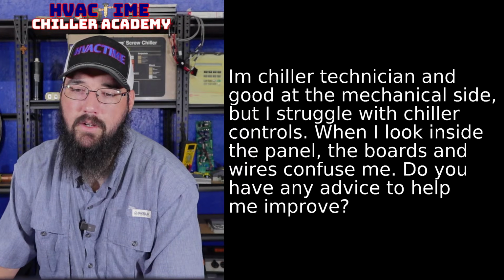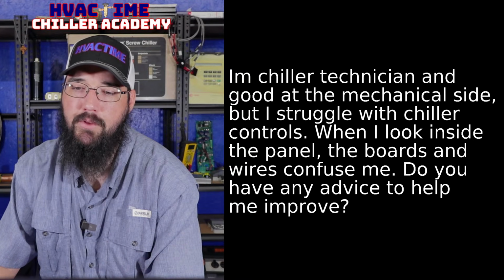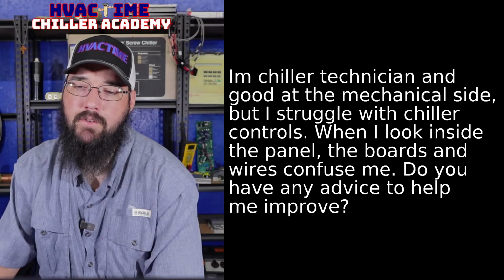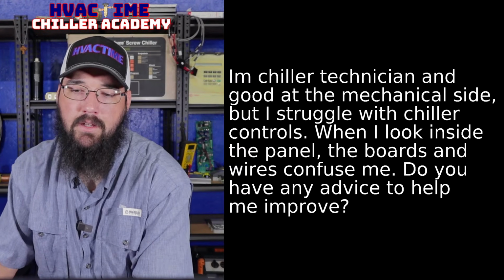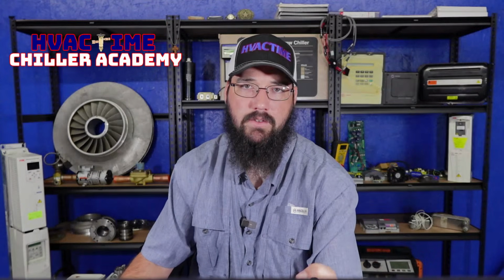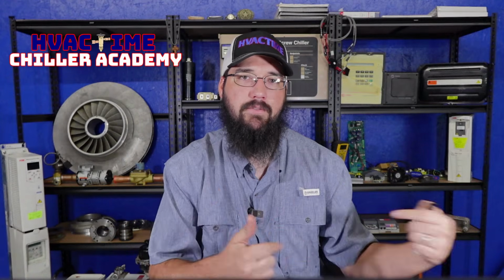Well, a locked up compressor would not cause the fuses to blow on the power assembly, because then the question I would have would be, do you even get into a charge of the DC bus? Does your DC bus charge? If you're blowing fuses before you even get to the charge cycle, before that drive ever outputs to the motor, it's got to charge that bus up. So probably not the motor. If you're popping the line fuses coming in, it's somewhere from the drive back to line, something in between there is going on.